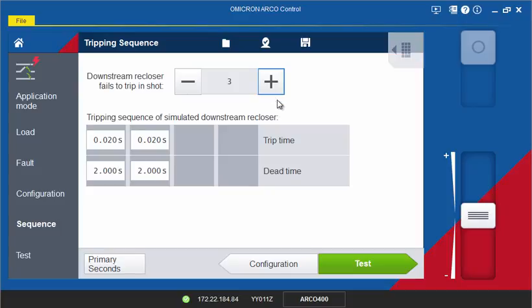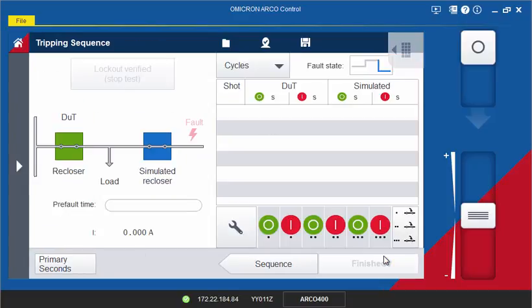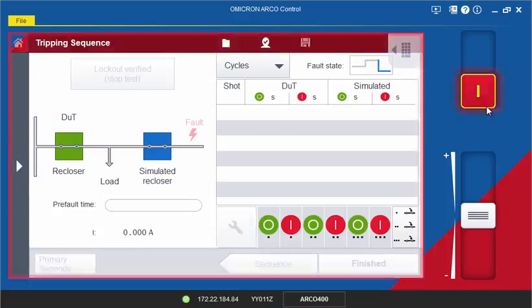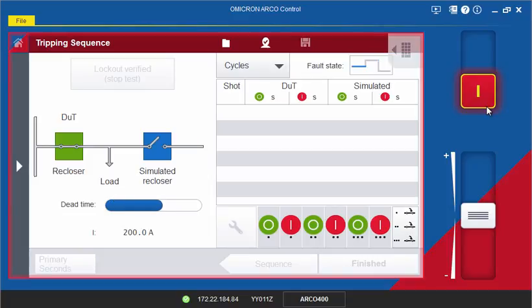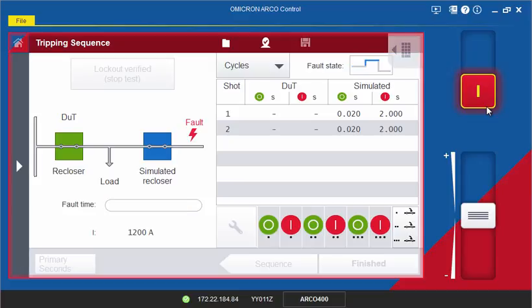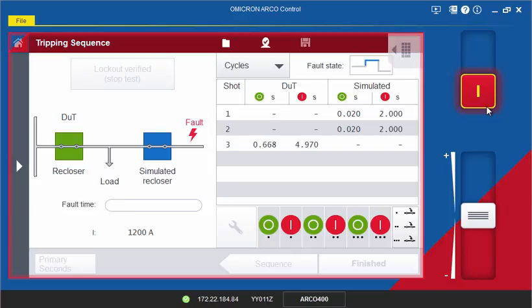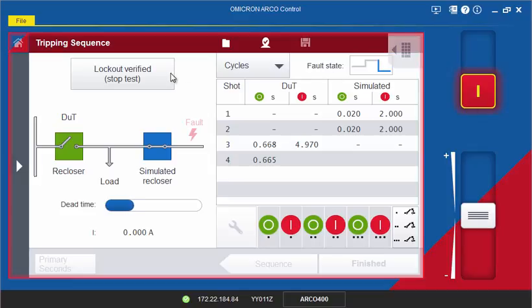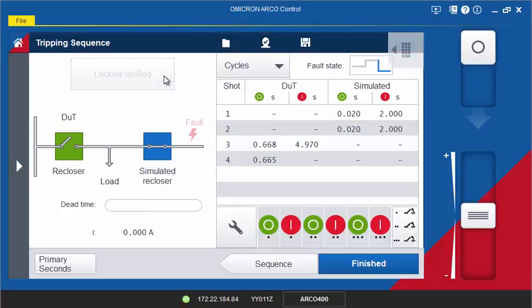Now start the test and watch the simulated behavior states of the downstream recloser. The recloser control under test should sense the downstream operations of the recloser on the simulated fault and take those recloser operations into account. If in this example the recloser control under test is set to four shots to lockout, it would sense the two reclosings of the downstream recloser and only reclose one time before locking out.